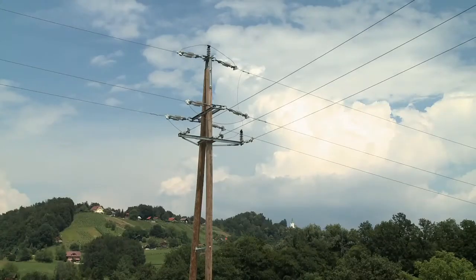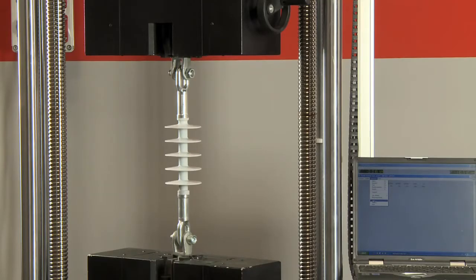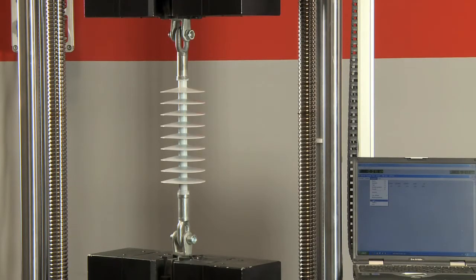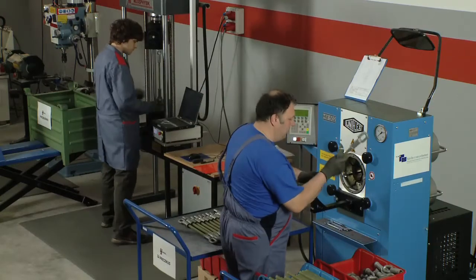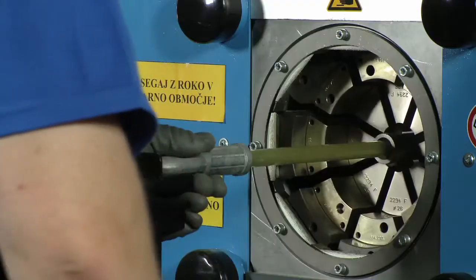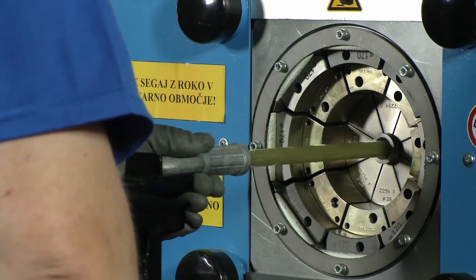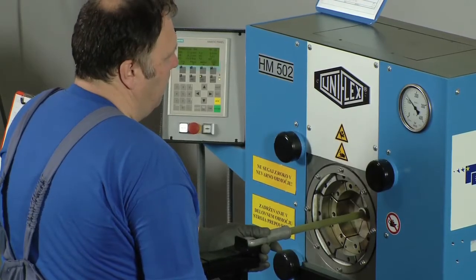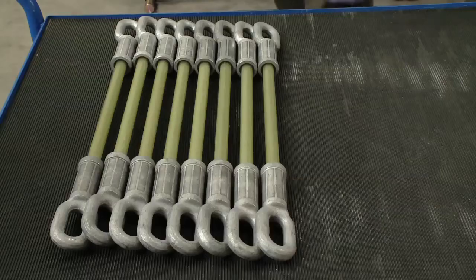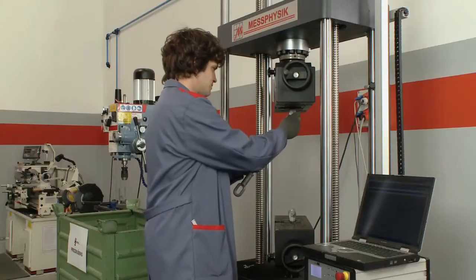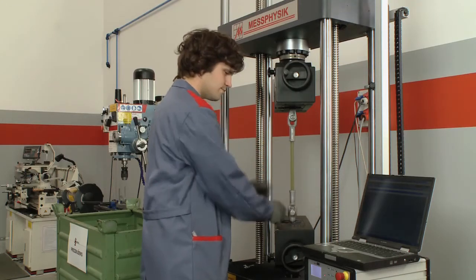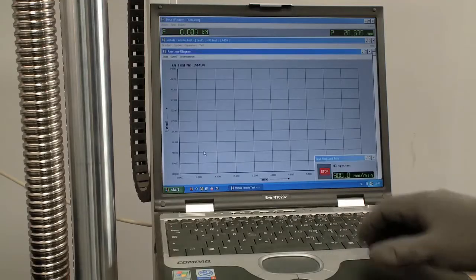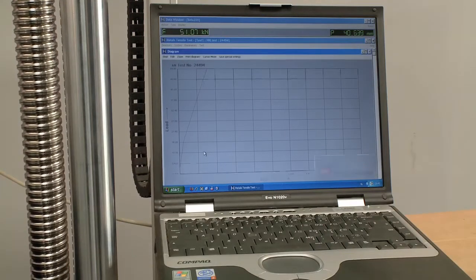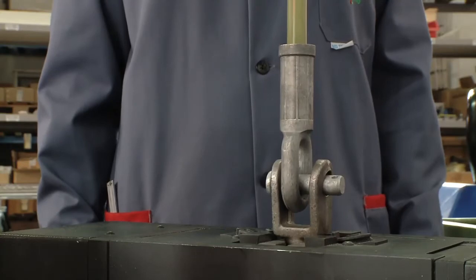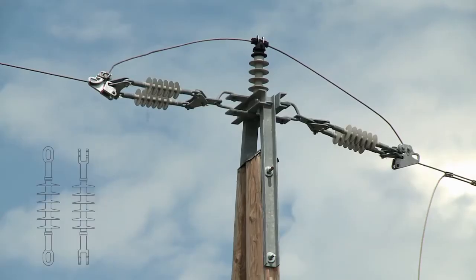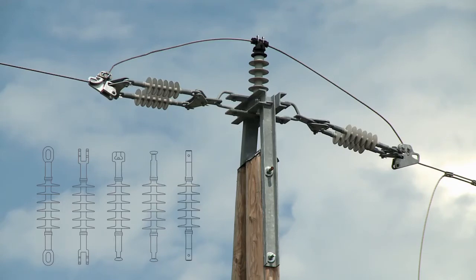Our production line also encompasses tension composite insulators with a creepage distance of up to 1,200 millimeters. Particular attention in the manufacturing process is given to the pressing of metal fittings onto the core of the insulator. A highly modern hydraulic machine with 8 pressing jaws and 3 different pressing modes is used for this purpose. In accordance with the standard, we also perform pressure controls on each insulator before siliconizing. Tension composite insulators are available with various end fittings in the form of an eye, clevis, socket or ball, as well as operating rods.